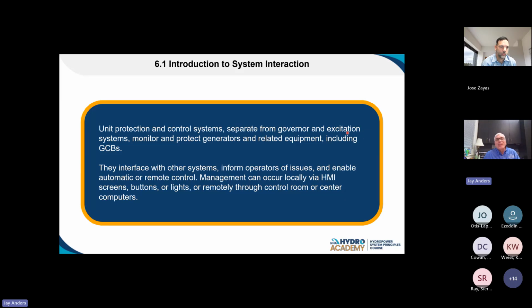The exciter is the same thing—it looks for external input to raise or lower voltage, but internally it has all kinds of protective features. Governors, exciters, and other control systems all tie back to relays that ultimately open the generator circuit breaker. That breaker provides isolation in the event of a problem internal or external to the system, getting the unit off the grid if the grid's going crazy, or getting the generator off the grid if the generator's going crazy.